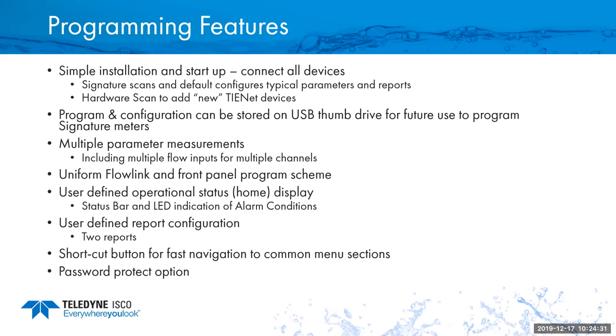Connecting via FlowLink into the device and seeing what you see on the front screen are exactly the same programming scheme, if you look at it that way. What you see on FlowLink matches exactly what you see on the home screen or when you work through with your keypad buttons. You're able to do those two reports, like we said. Most people do a daily and a monthly. You're able to set the start times. Say you want to do 8 a.m. or midnight, you can set that as well.